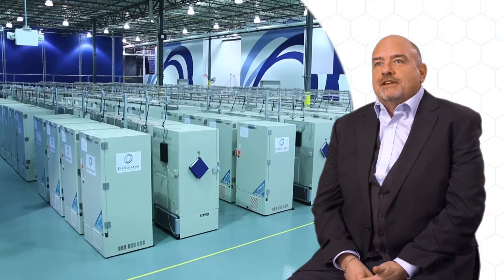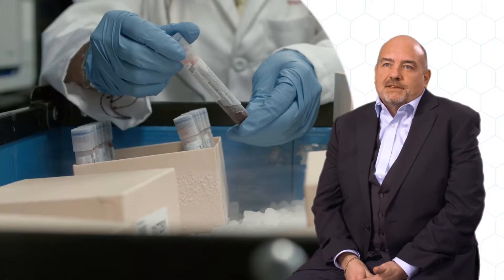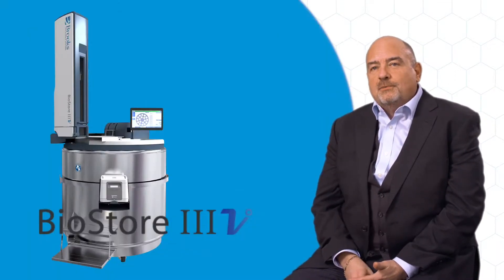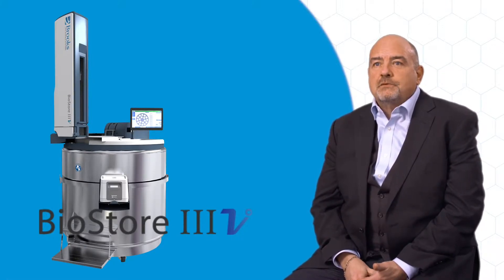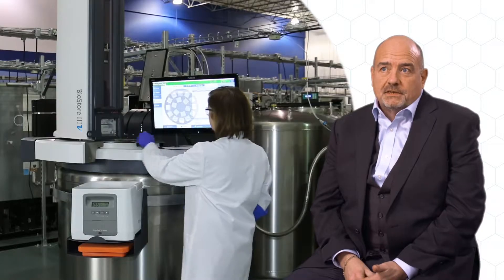Minus 80 centigrade is a very common storage environment in many laboratories and institutions worldwide. It's basically a mechanical equivalent to dry ice, and to address this requirement the Biostore 3 Cryo is now available with a temperature-settable option, allowing for the full automation benefits at any temperature from minus 20 to minus 150 centigrade.